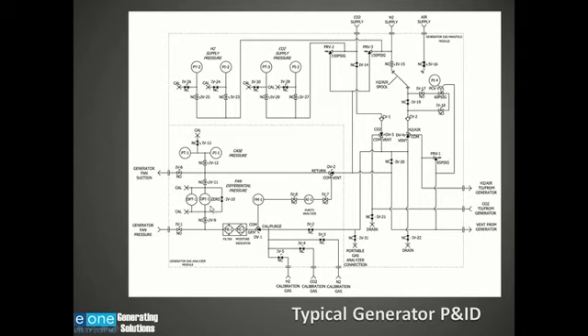Here we have a differential pressure indicator and transmitter. Indicator for local indication, transmitter to go back to the control room. Once again, we have calibration ports so that we can calibrate this unit without taking the unit offline. Now, when the generator fan is turning, when the generator is at full speed, we will have a fan pressure and a fan suction. That will create a flow through our analyzer that measures hydrogen purity. So I've got a fan pressure, hydrogen will enter through here, go through a filter moisture indicator, set the flow through this flow meter, through the analyzer, back to the generator.